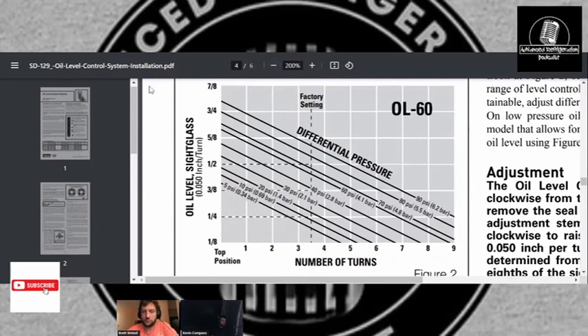But these are dependent on this differential pressure. So if your differential pressure is off or nothing or is too high, it's going to change your oil level in the compressors.